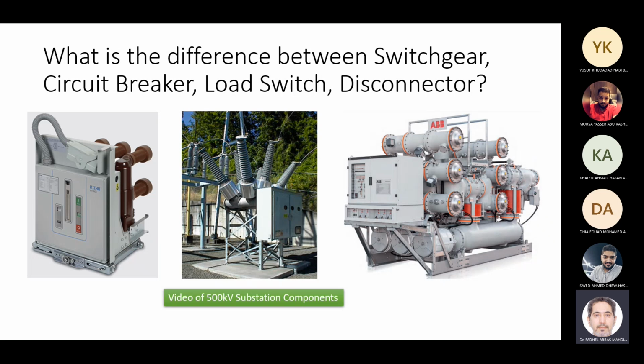So they provide large gaps, distance between the contacts, so that the two sides of the isolator, the two components at the two sides of the disconnector, are physically isolated. This could be either motorized or manual. But they are not used even to switch a load. Normally we switch a breaker first, then we disconnect the circuit through the disconnector.